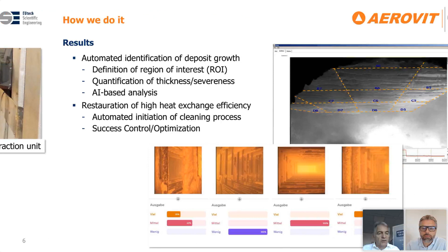So what we are doing, actually, we do automated identification of the process. We define regions of interest. We quantify the process. And what we apply is also artificial intelligence to analyze the severity of the sooting, because you can see a lot from the surface. If it's already molten, if it's a loose sintered material, which easily can be cleaned up, or you have to do it twice, 3 times in a row, that all you can take from the picture. So the artificial intelligence gives you information that this is clean, this is sooted, and this might be dangerous in the near future. So by this, we can automate and initiate the cleaning process and can control the success of the cleaning.